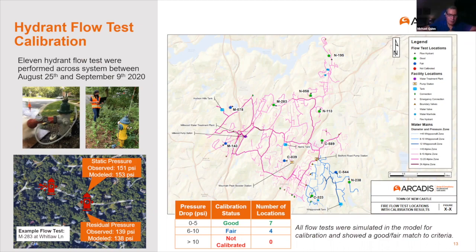With the testing you were doing, was there any way to specifically substantiate the fire flow in a certain section or on a hydrant? But you answered the question. It's all pressure driven, but I was just curious. Yeah, and for other systems, sometimes we do use, like you can see from the picture, the 4-inch at the front. Sometimes we'll open up even multiple ports just to try to get more flow out. But in this condition, we wouldn't have gotten that much more out.